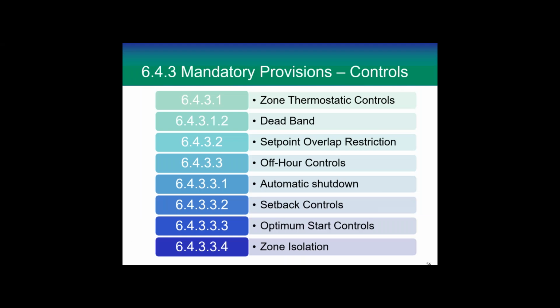Mandatory provisions, controls. In the mandatory section, after we regulate equipment, we put most of our controls under the mandatory. So we have zone thermostatic controls, dead bands, set point overlap restriction, off-hour controls, automatic shutdown, setback controls, optimal start controls, and zone isolation. These have been around forever.